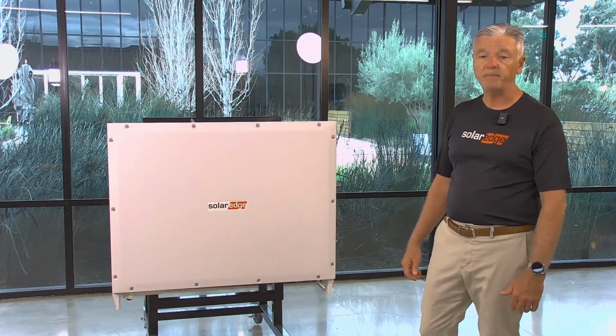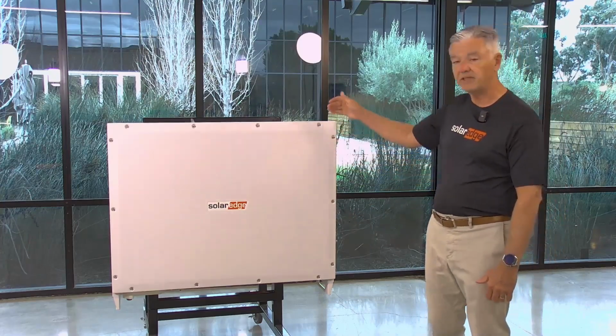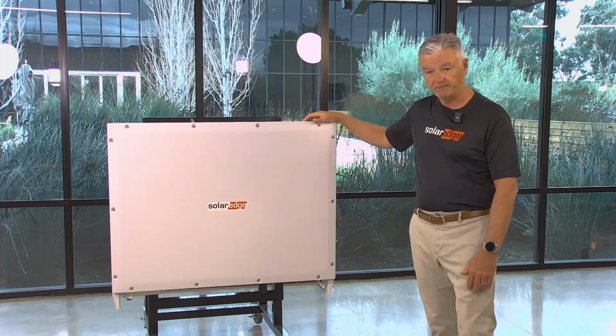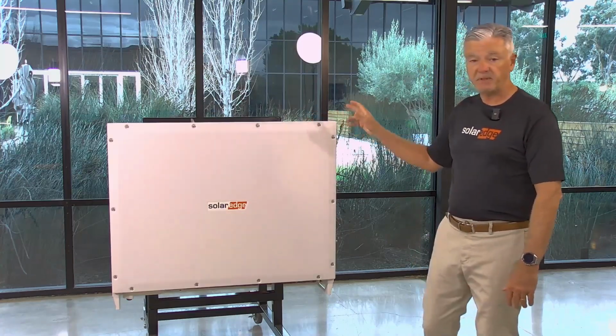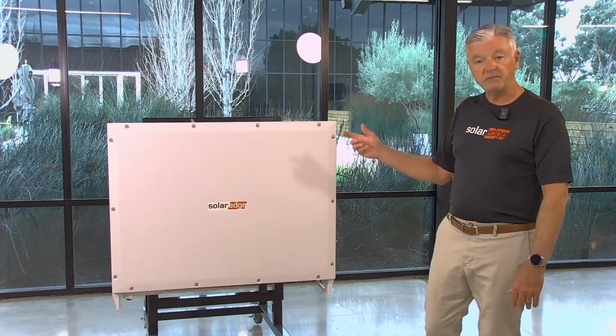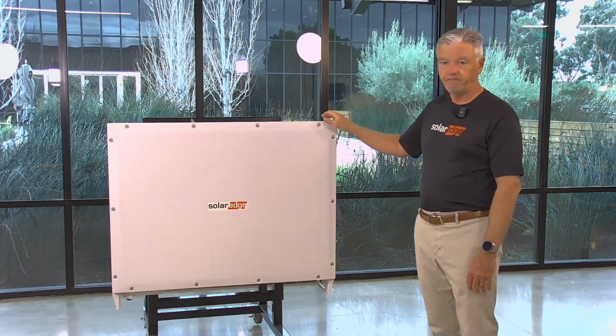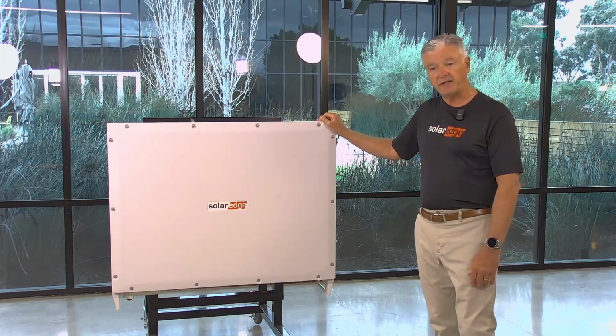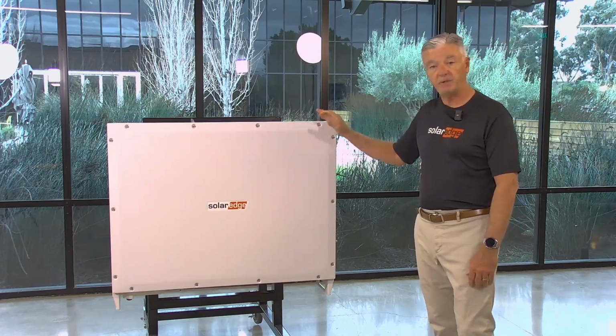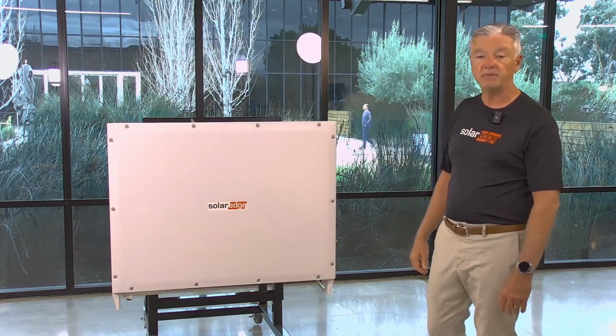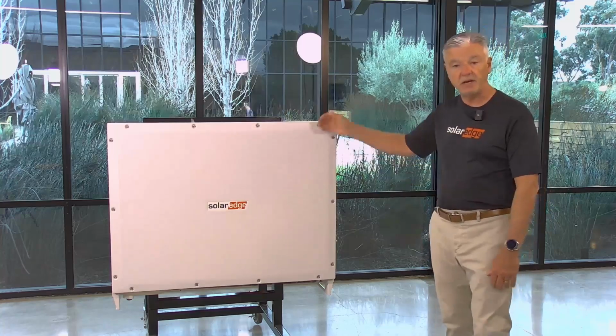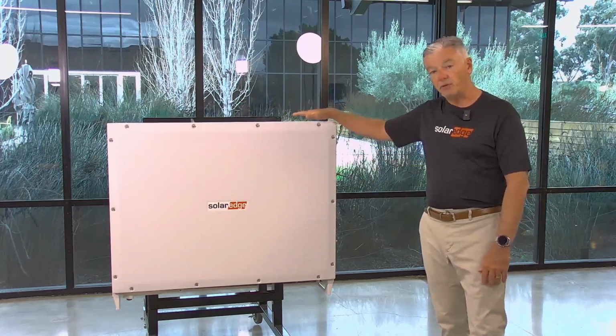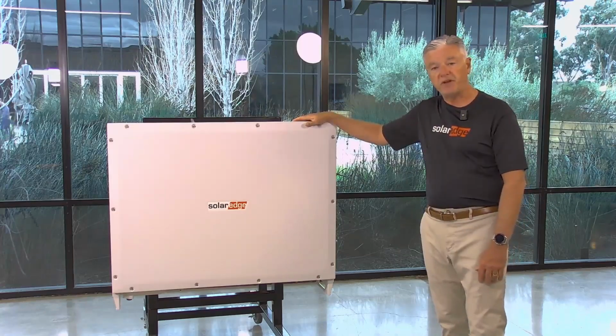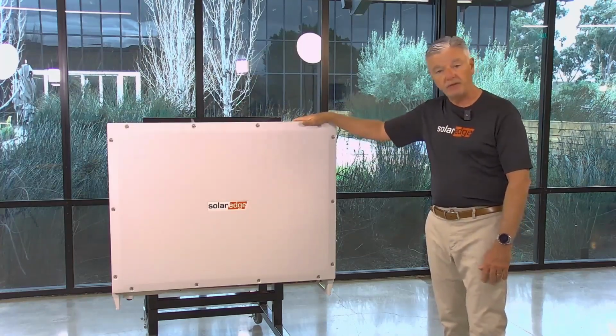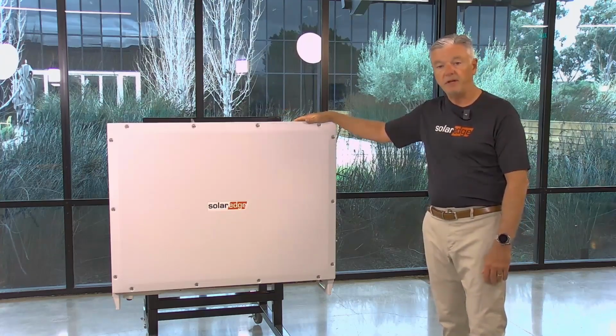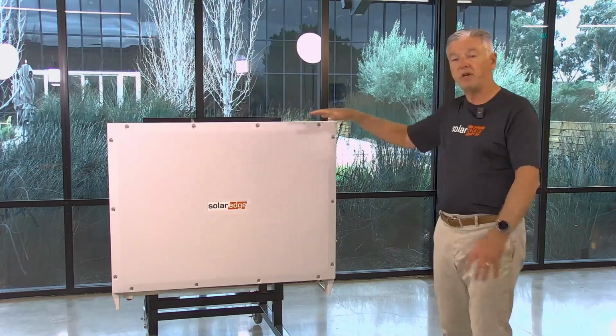Grid connection is 3-wire, and you can put 200% oversizing on the DC side up to 660 kilowatts. Communication options are CAN bus between inverters, RS-485 Modbus, Ethernet and cellular for external devices. It carries all the smart inverter certifications that you would expect, like UL 1741SB and the latest IEEE 1547 grid interconnection requirements. It also includes features like PID mitigation, and it's also ready for storage. It has features like commissioning from the sun that allow you to commission the inverter with the DC side when you don't have AC present at the site. And it also features central commissioning where you can commission a group of inverters all together.